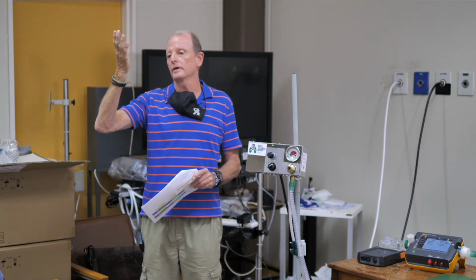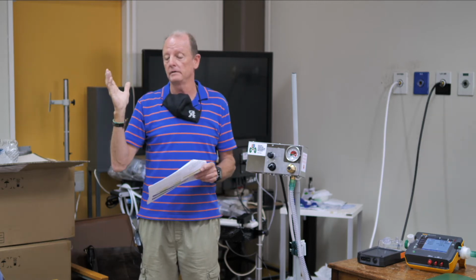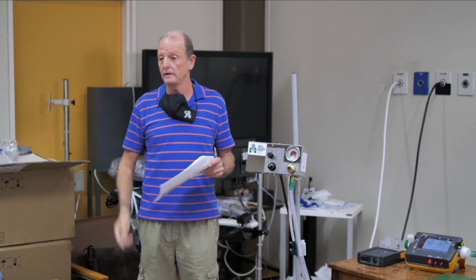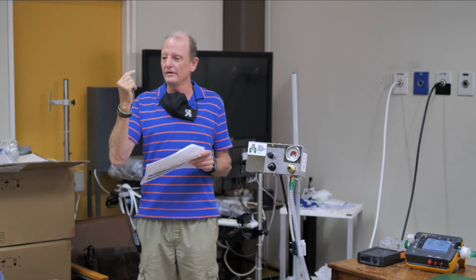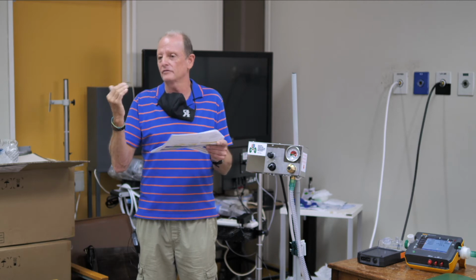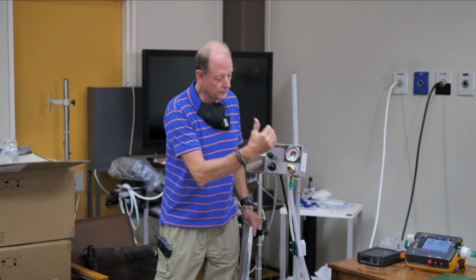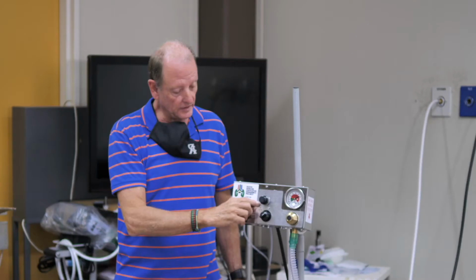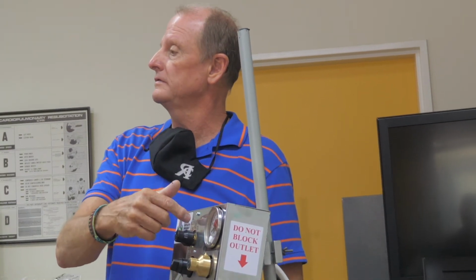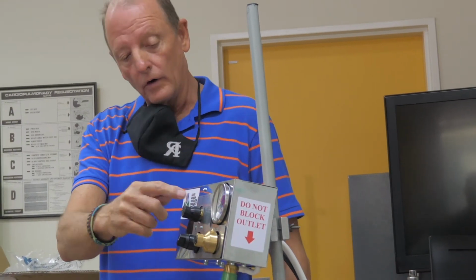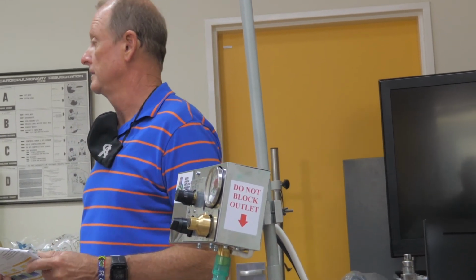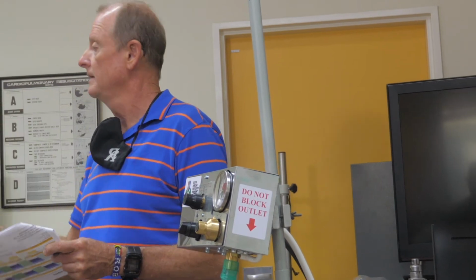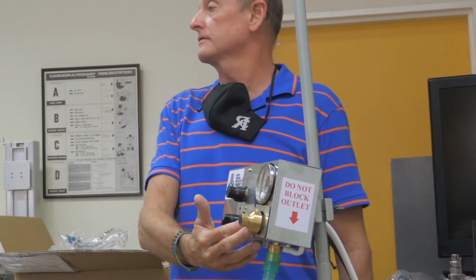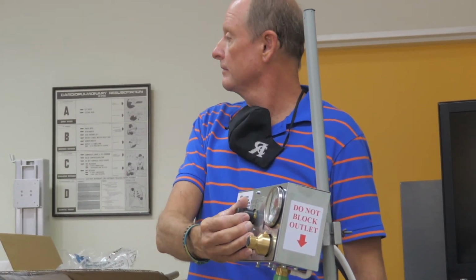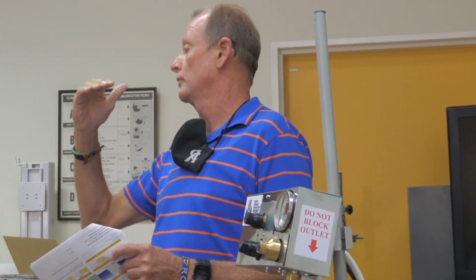You can check 21%. I always do. I mean, by rights, there should not be any leakages there. You might have a very slight 23%, 22%. That is still fine. Okay? And then you go through again and you do your percentages, 40, 60, 80, 100 on your flow rate of 40. Then you have a flow rate of 60 and you go exactly the same again. 21, 40, and record all those.